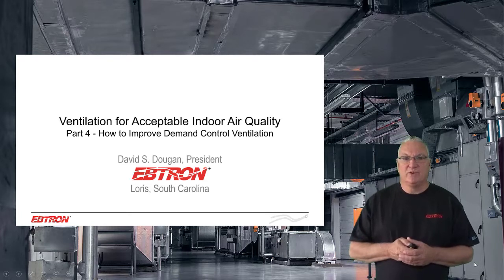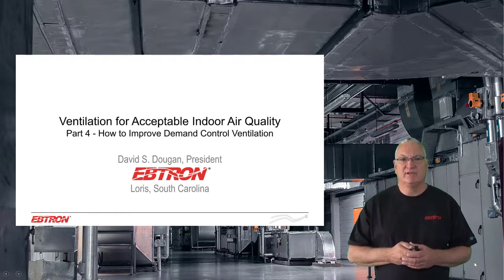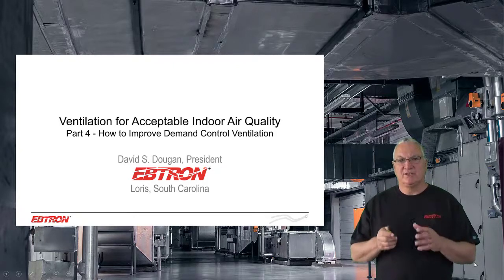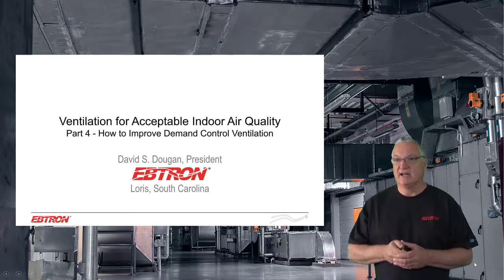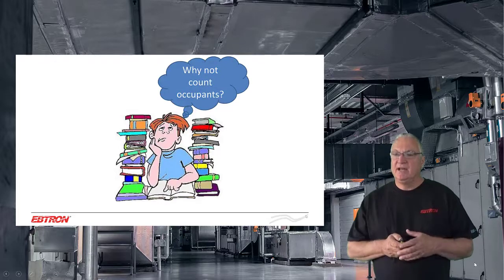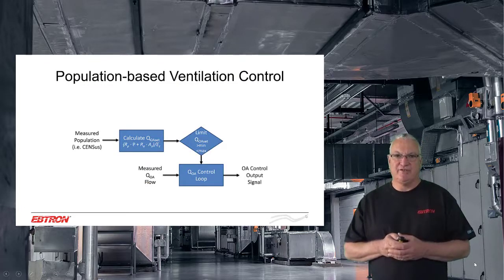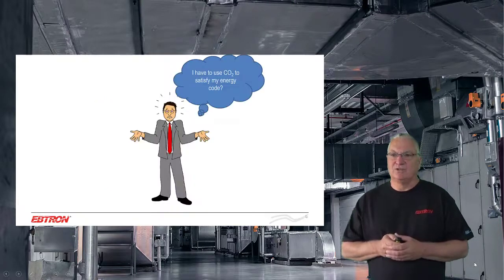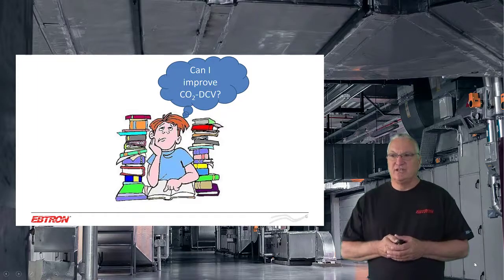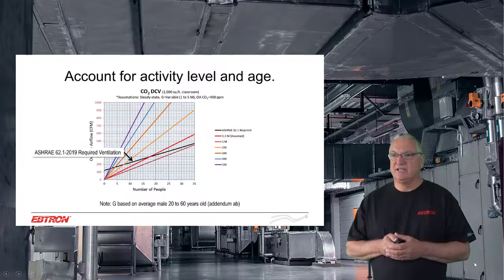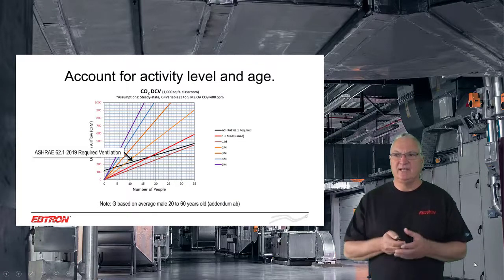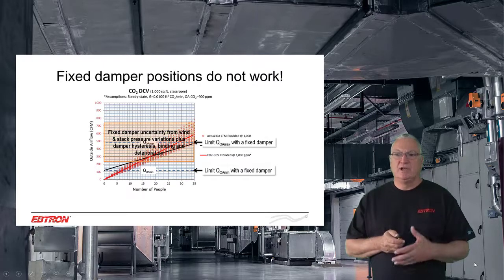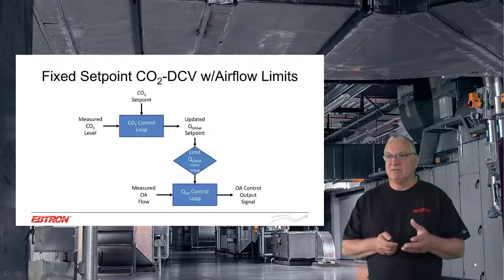When we get to part four, demand control ventilation really does make sense on a lot of spaces, particularly high occupant density spaces with extreme population variability. We want to go through how to improve it. We're going to talk about occupant counting, give you a strategy for occupant counting, and show you some of the uncertainties there — including the fact that there's a lag error. For those who have to use CO2, we're going to improve CO2 DCV, talking about accounting for activity level and age, and then setting limits — not with dampers, because there's so much variability, but with airflow measurement.